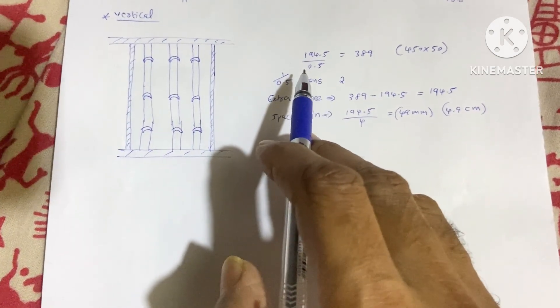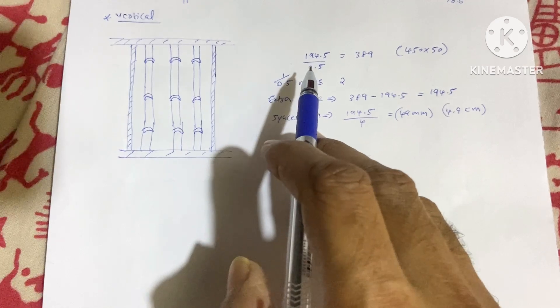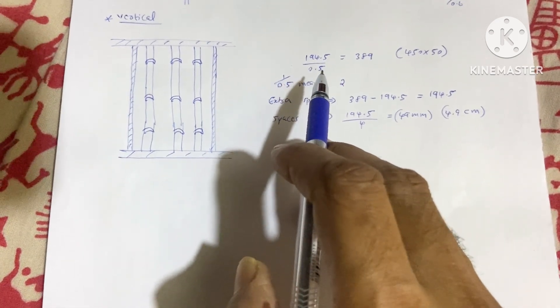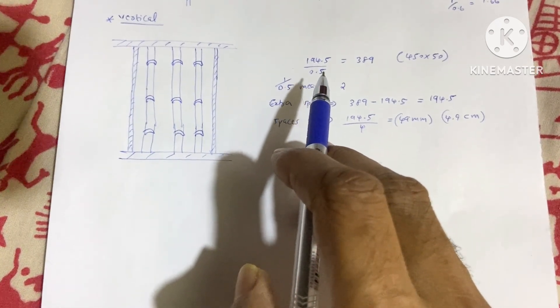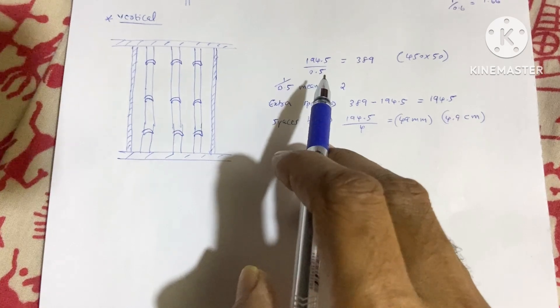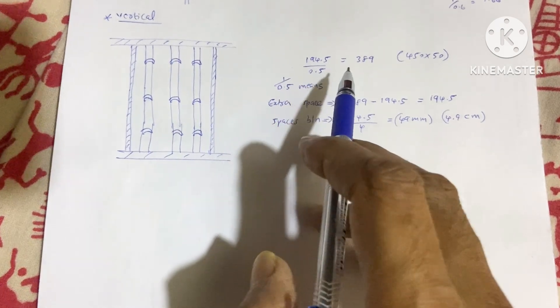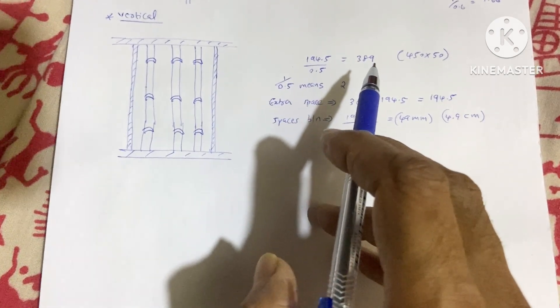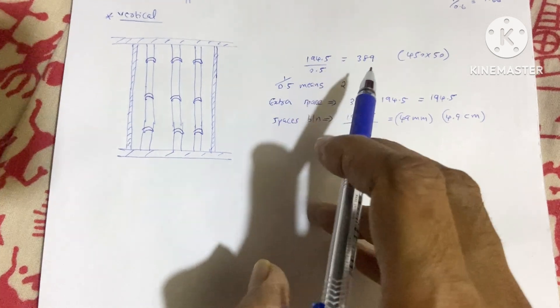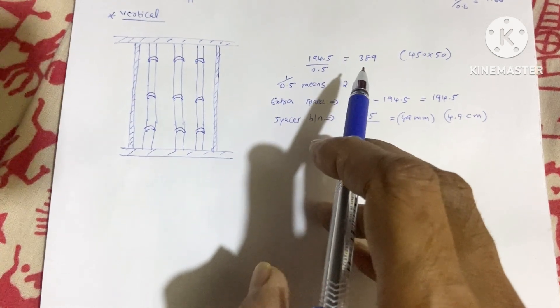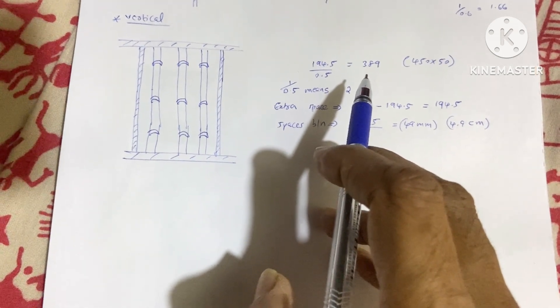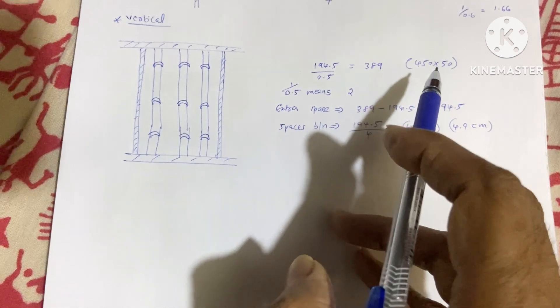For the vertical cable tray, we use a safety factor of 0.5 instead of 0.6. Dividing 194.5mm by 0.5 gives 389mm. Since 389mm is not a standard size, we again select a 450×50mm cable tray.